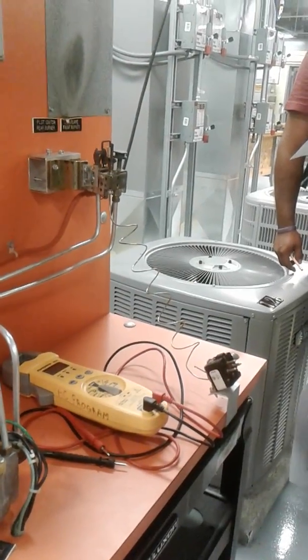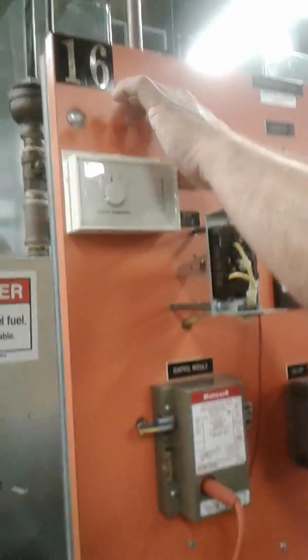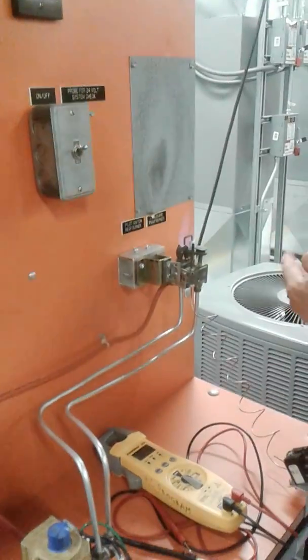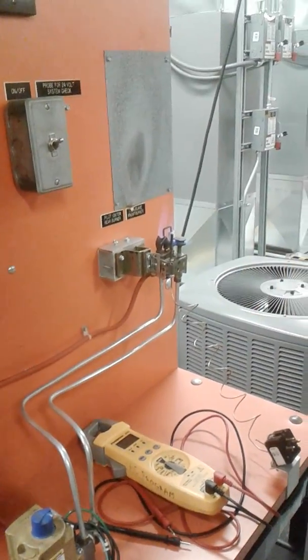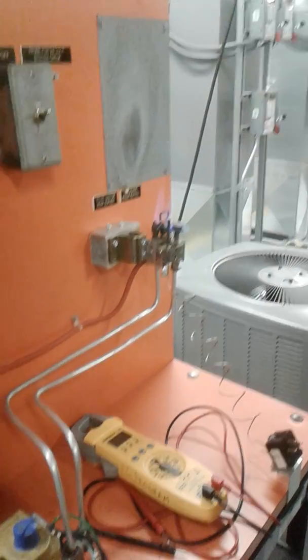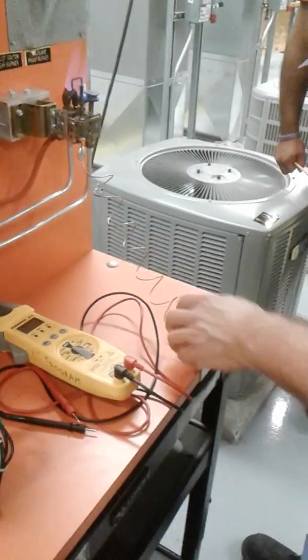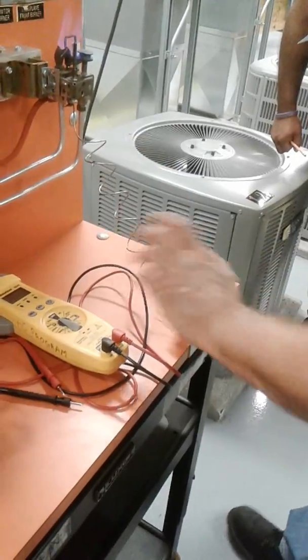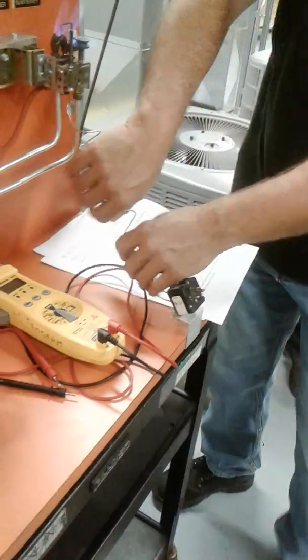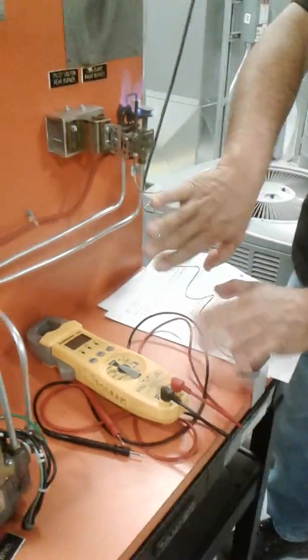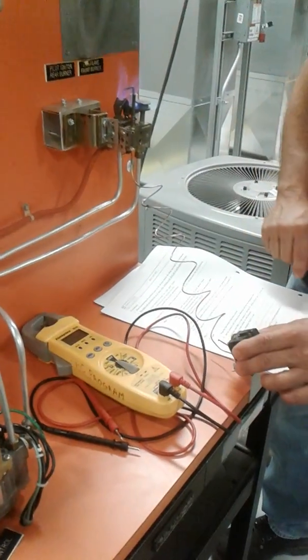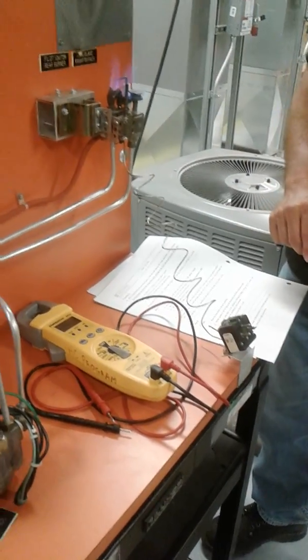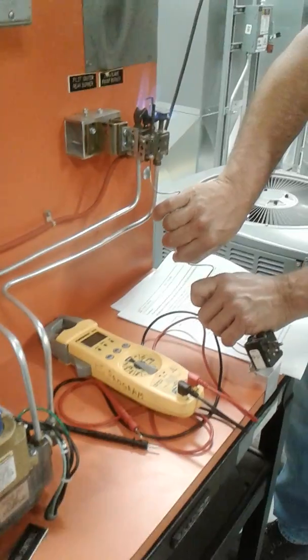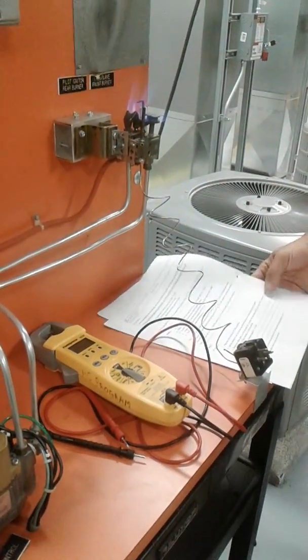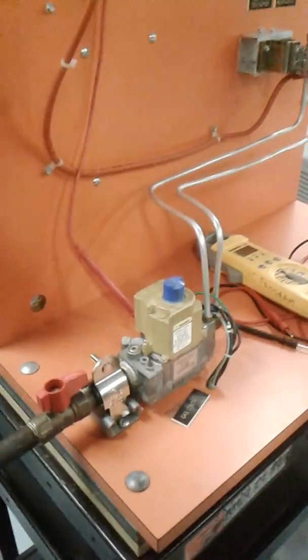So what happens is, we call for heat. Spark, pilot, burner. Normal operating conditions. This is the mercury flame sensor. Just ignore this. We're not even using this anymore. Not even in the equation. We only had this here for that one lab that we did a couple weeks ago. So ignore this. Not part of it. Now we have our burner and it's running perfectly.